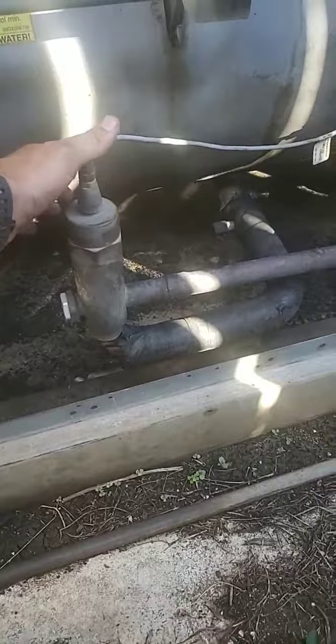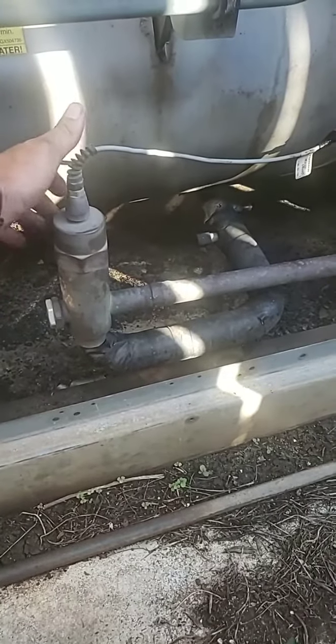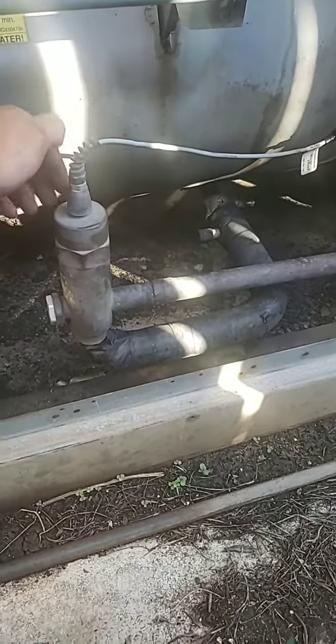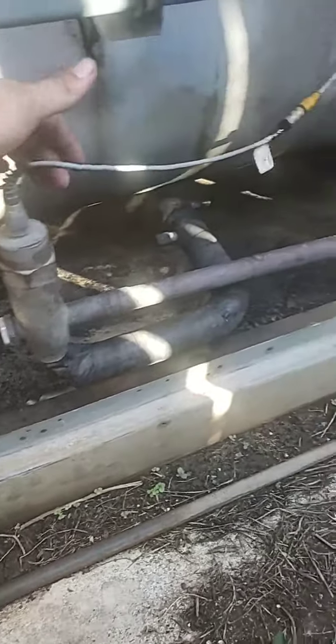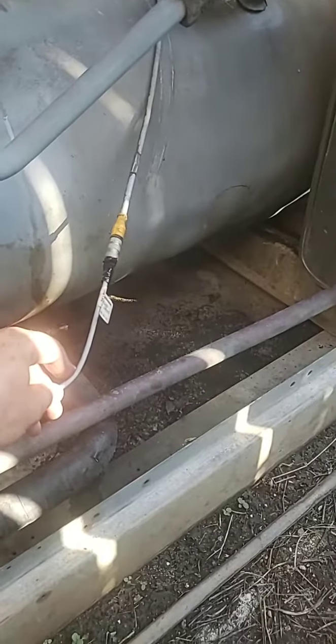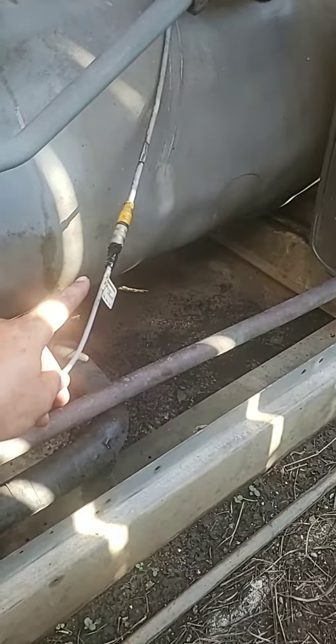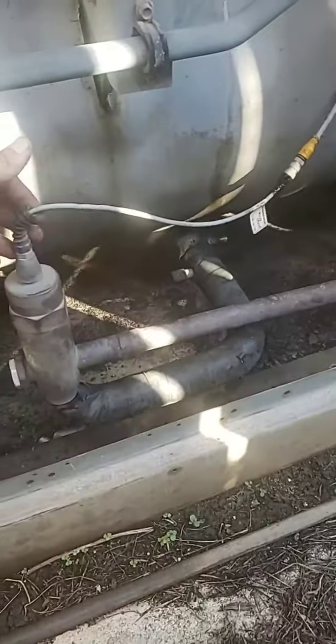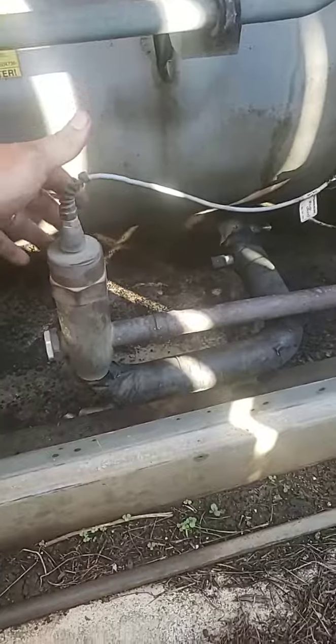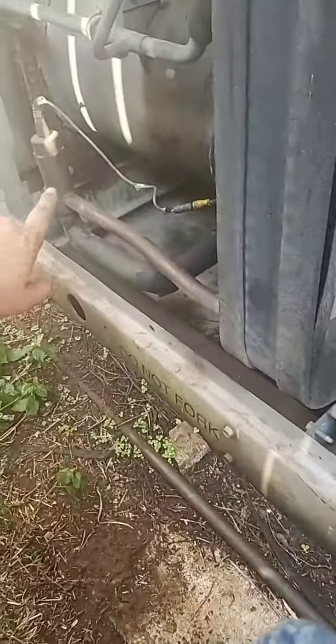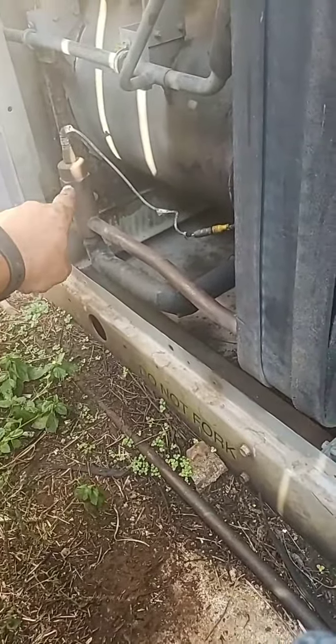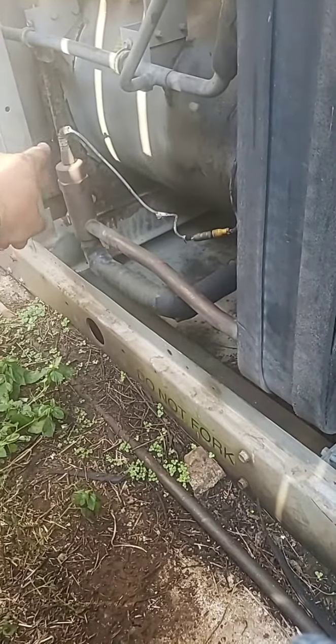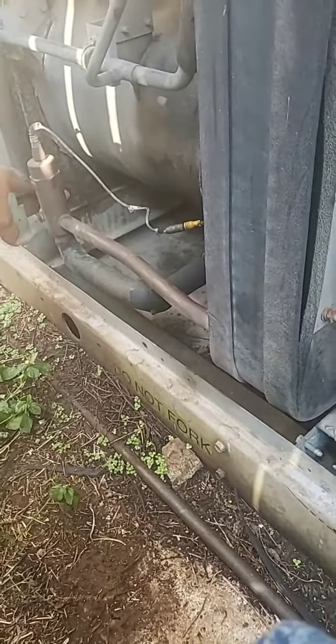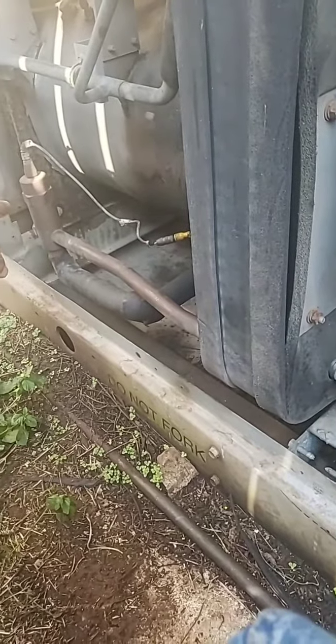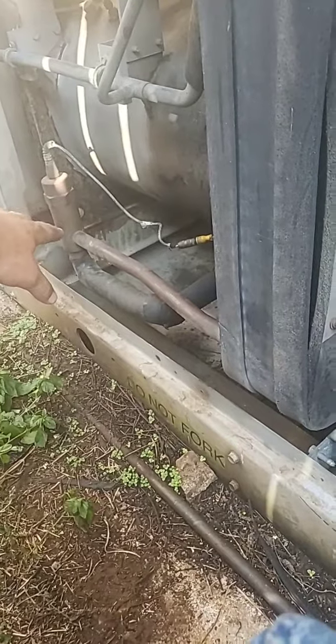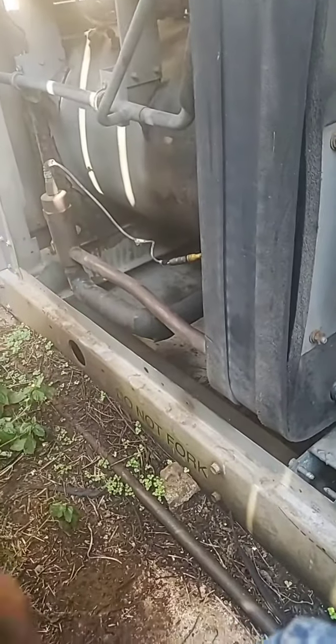These EXVs, I believe, are 15,000 steps total. They've got two little circuits inside. They've got a little quick disconnect connection that just threads apart and pulls off. Pretty easy to service, easy to troubleshoot. Funny thing is, that EXV on circuit B is actually sticking. I've got to replace the upper assembly and try to clean the housing. So that's a job coming up. I'll get some really good posts on that in the future. We've got to get it approved first.